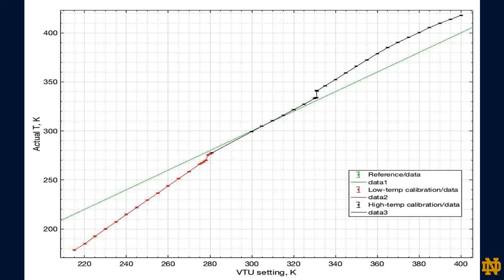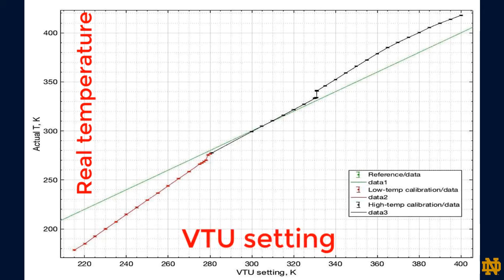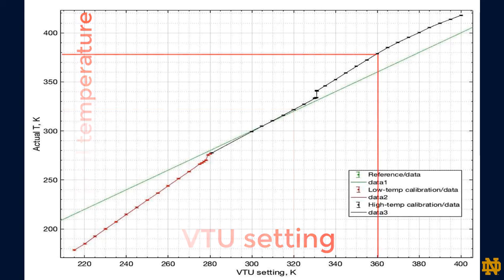All this time, when I was saying temperature, I meant actual real temperature of the sample. However, VTU of the instrument does not know the real temperature. It operates in relative units, which are close to real temperature in the ambient temperature region, but deviate significantly at high and low temperatures.